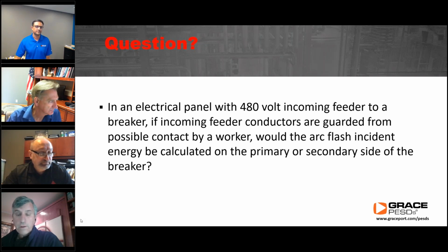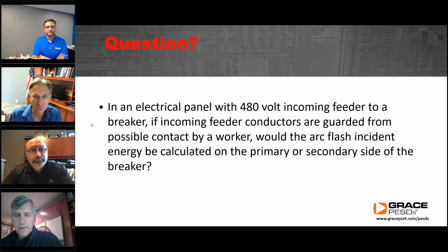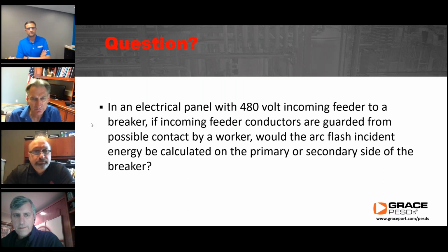Yeah, this is a loaded one as well. There's a few things to consider. From the engineering side, there are two schools of thought when you're modeling panels with a source or a main breaker in the panel. One school of thought is to assume that the main breaker would actually be able to clear faults on the load side of that breaker, and it would not fail catastrophically and produce an arc flash of any kind. The benefit of that approach is that the label on the panel will show considerably lower incident energy than if you did what they're suggesting here.